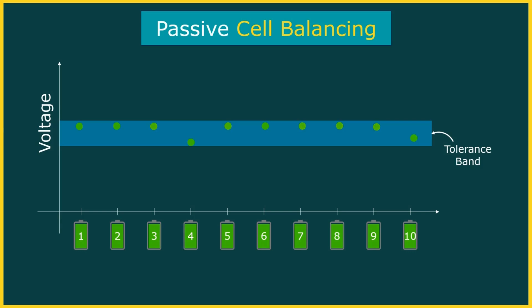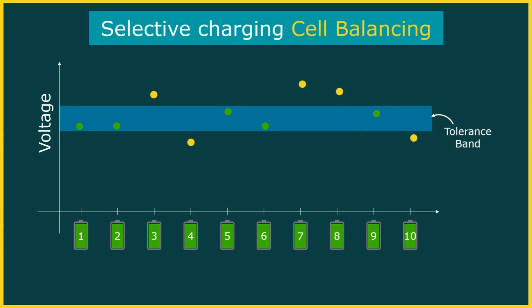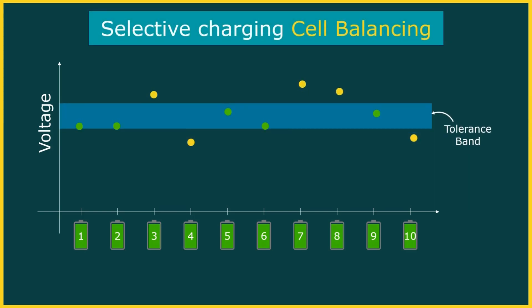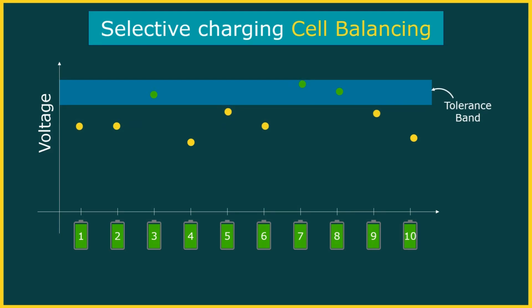To reduce that loss, there's another approach called selective charging balancing. Here, the BMS sets the tolerance band to the highest voltage cell. Low voltage cells outside this band, like cells 1, 2, 4, 5, 6, 9, and 10, are selectively charged until they are back in the tolerance band. This method saves more energy than passive balancing, but it's more complex to implement.